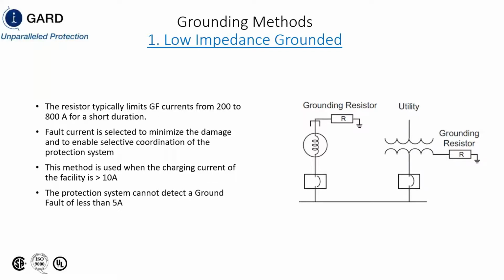And if your protection system is going to be through conventional relays, then the ground pickup of conventional relays using residual current is going to be minimum, or the minimum value is going to be 20% of the let-through current of the CT. So if you have 2,000:5 amp CTs, your minimum pickup is going to be 400 amps. So this is why there's such a great difference between a high and a low resistance grounded system.